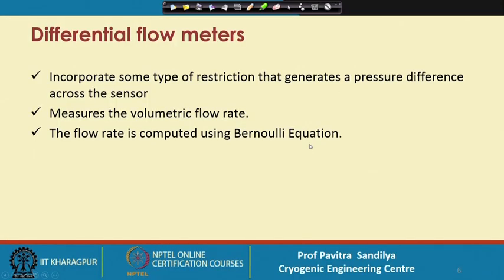We put some kind of restriction on the flow path for pressure drop measurement, and then this pressure drop is measured by some sensor. After this, whatever delta P — differential pressure drop — is measured, we develop a theoretical formula to get the volumetric flow rate. This flow rate is generally computed by the Bernoulli equation.